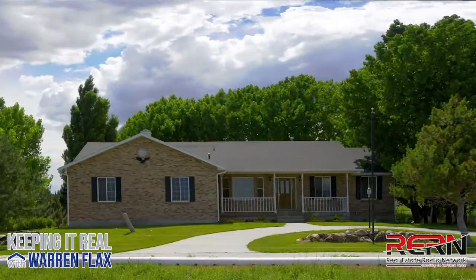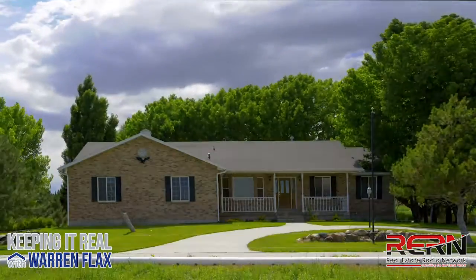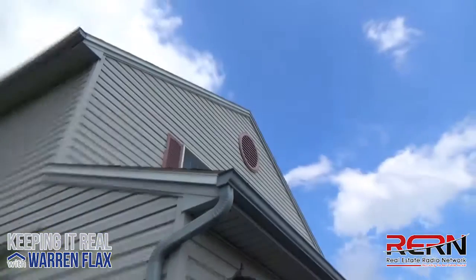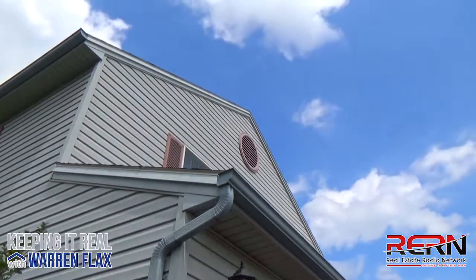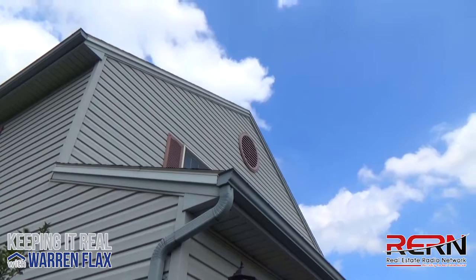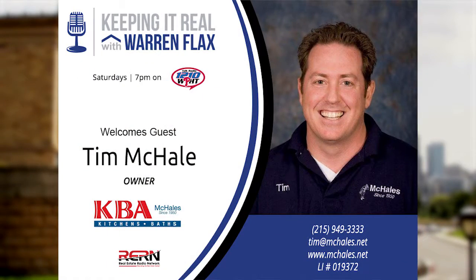In our region, a lot of the electrical systems come from the street as opposed to underground - it's an aerial electrical service. There's a wire that runs down the side of your home called the service utility cable. The sun beats down on that for years and years, and it corrodes whatever insulation is holding onto the outside of that wire and protecting it. At that point, just like a candle wick, water will get in there and suck it right down into your electrical panel, corroding your bus bars - that's where the breakers sit into. They'll create hazardous conditions, not only for you, but also for your electronics, your appliances, and anything else that might be plugged into those circuits.